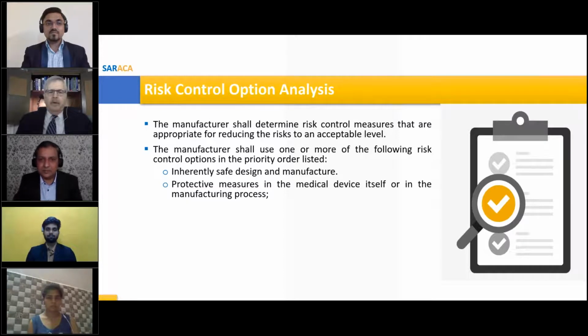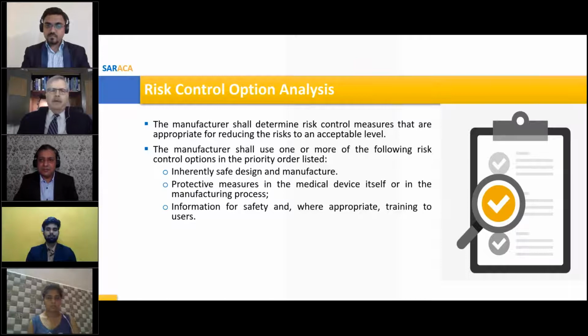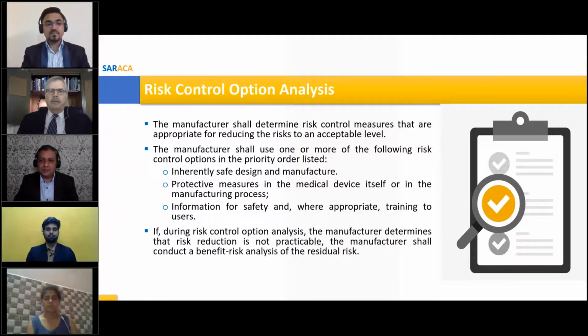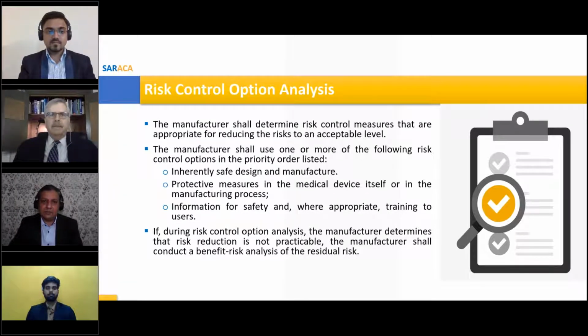One thing that's very important as part of your design process, which may or may not be included now, is that before you can release your product into commercial distribution, the last phase of your design process needs to include a review of the risk analysis, and is it adequate for the device, and did you meet all your goals?